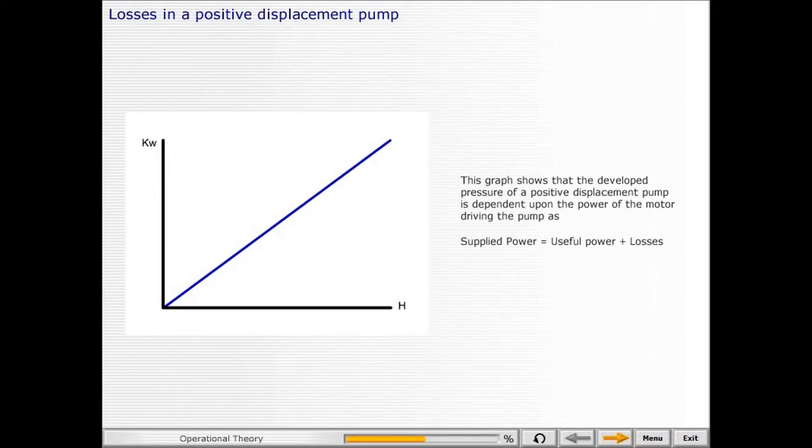This graph shows the developed pressure of a positive displacement pump is dependent upon the power of the motor driving the pump, as supplied power equals useful power plus losses. For a positive displacement pump, losses are mainly mechanical, with the exception of a small loss due to leakage.